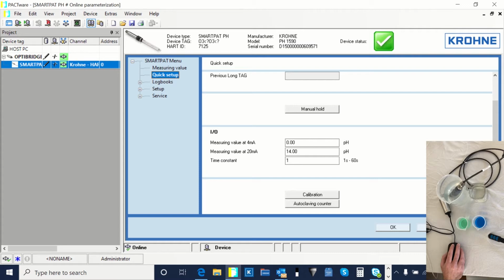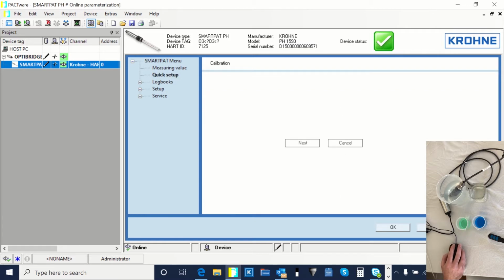and using a HART communicator over a 250 ohm resistor while the probe is online, then yeah, you would need to hold the last value so it doesn't play around with your DCS and your online 4 to 20 milliamp. So we'll just start our calibration. Manual hold, we're going to click no as just discussed. Temperature compensation, automatic, yes, we'll select that.